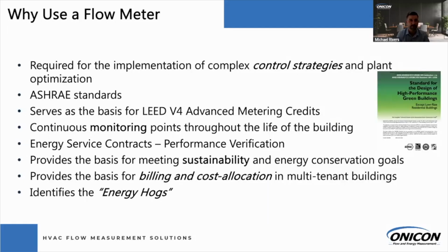All right, so why are we using flow meters? I think a lot of different reasons of what people are doing with flow measurement, but I really kind of break it down into three different applications: monitoring, controlling, and billing. It's nice that from a monitoring standpoint, having continuous monitoring points throughout your system to really understand where the flow and the energy measurement is going. Also control. When do I want to turn on that second chiller? When do I want to turn on that third chiller? Or when do I just want to make sure I'm maintaining a specific flow rate into a chiller? So using this measurement for your control strategies.